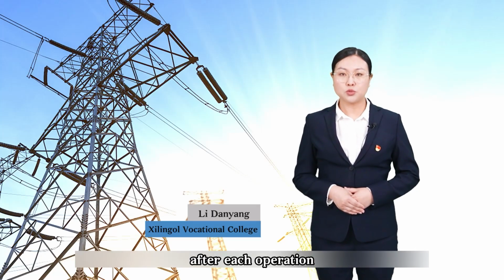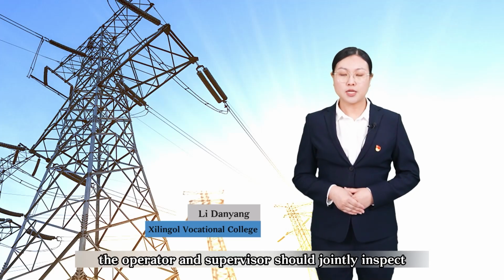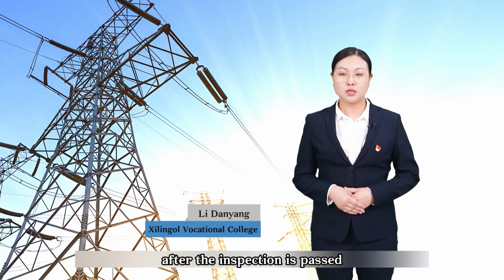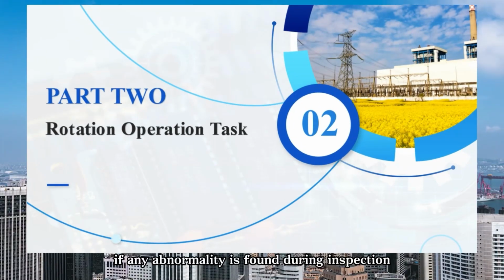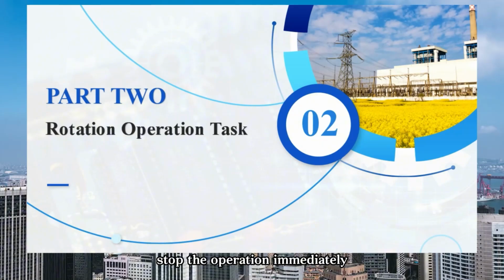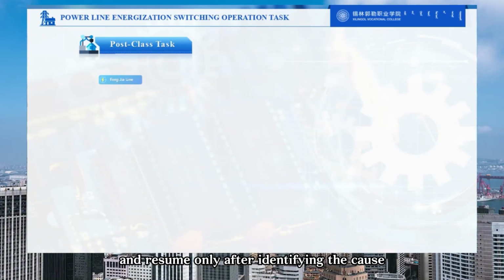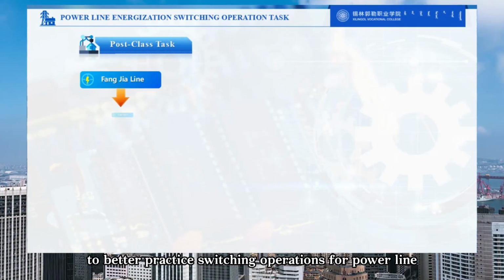After each operation, the operator and supervisor should jointly inspect the result. After the inspection is passed, the operator takes out the interlock key and hands it to the supervisor.